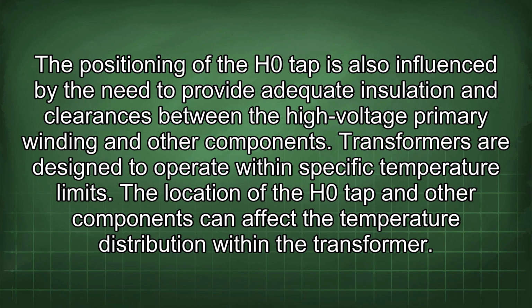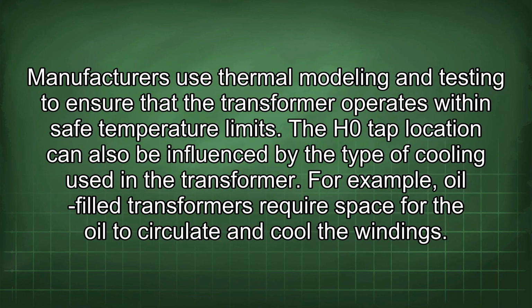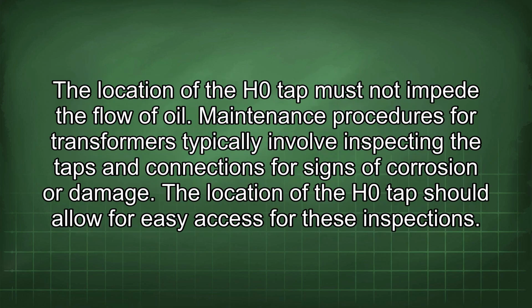Transformers are designed to operate within specific temperature limits. The location of the H0 tap and other components can affect the temperature distribution within the transformer. Manufacturers use thermal modeling and testing to ensure that the transformer operates within safe temperature limits. The H0 tap location can also be influenced by the type of cooling used in the transformer. For example, oil-filled transformers require space for the oil to circulate and cool the windings. The location of the H0 tap must not impede the flow of oil.